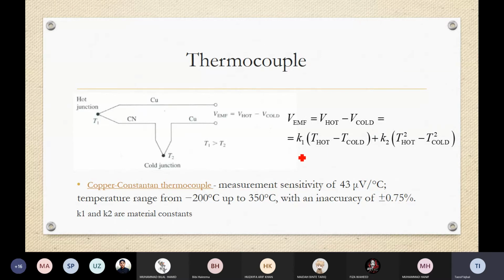So K1 is the material constant for one type of material, and then we have K2 for the other type of material. And then we basically take the difference between the temperature of the hot side and cold side, and this change in temperature multiplied by K1 gives us the EMF voltage on the copper side. Similarly, second is the non-linear term, which also gets modified by the constant for the constantan material.